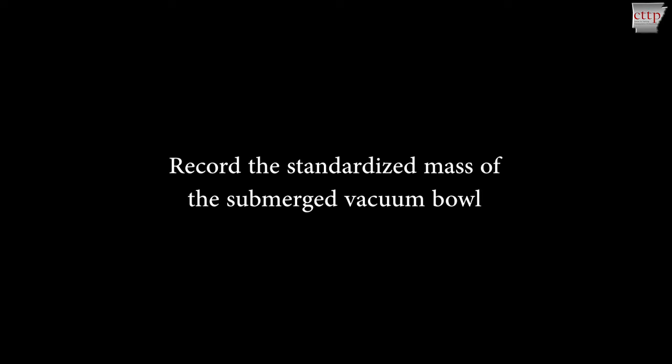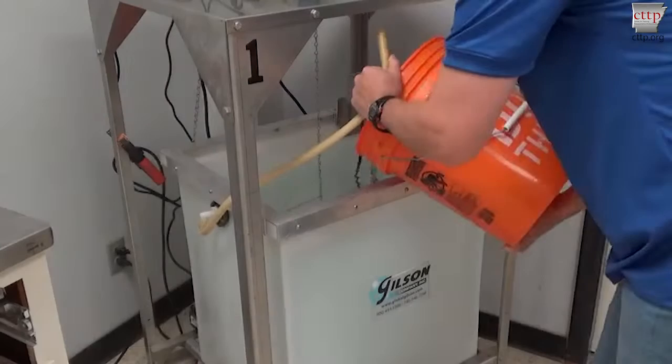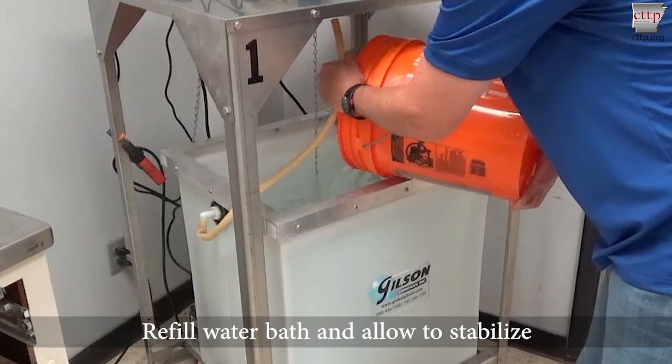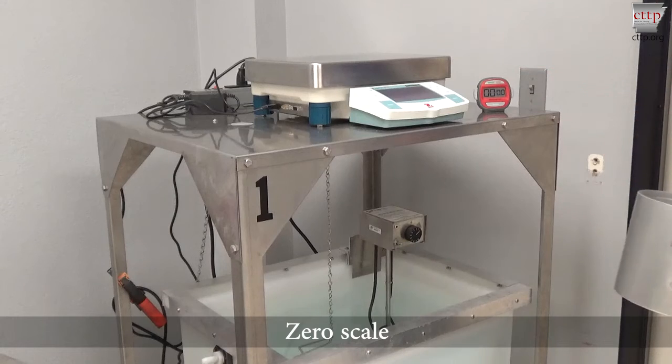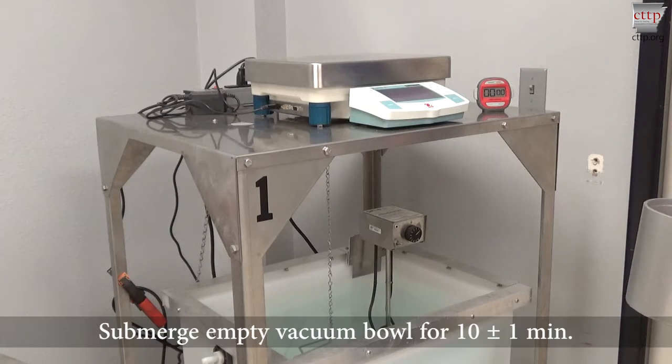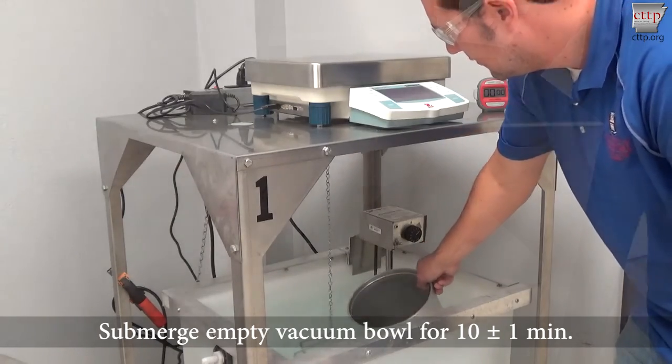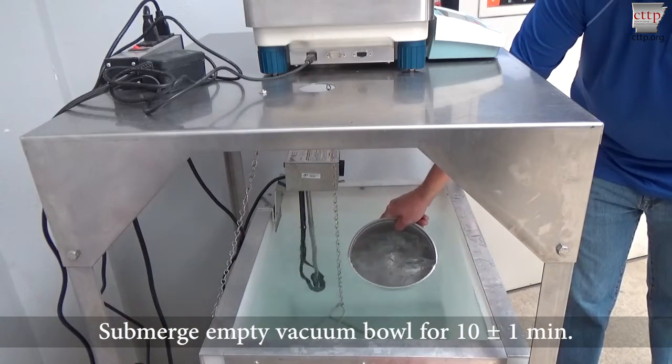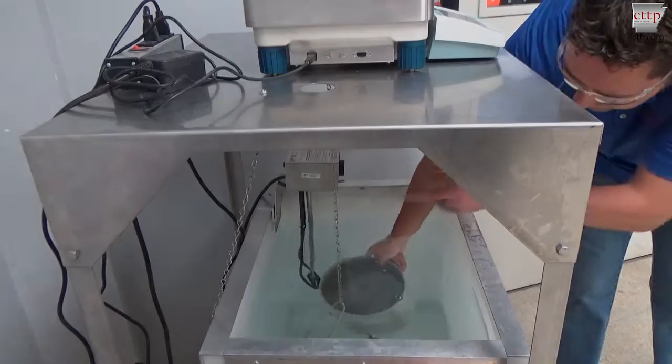To check the standardized mass of the submerged vacuum bowl, refill the water bath to overflowing and allow the water level to stabilize. Zero the scale. Submerge the empty vacuum bowl in the water bath for 10 minutes. Record the submerged mass of the empty vacuum bowl.